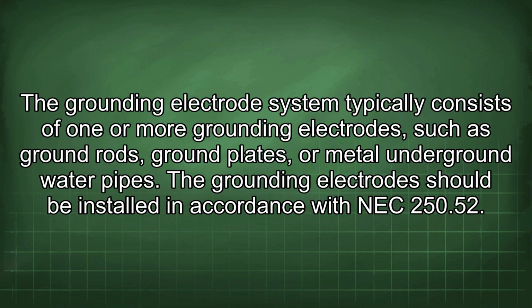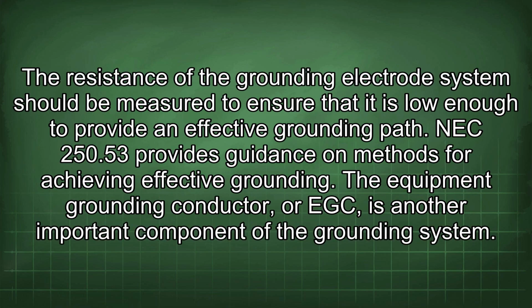The grounding electrode system typically consists of one or more grounding electrodes, such as ground rods, ground plates, or metal underground water pipes. The grounding electrode should be installed in accordance with NEC 250.52. The resistance of the grounding electrode system should be measured to ensure that it is low enough to provide an effective grounding path. NEC 250.53 provides guidance on methods for achieving effective grounding.